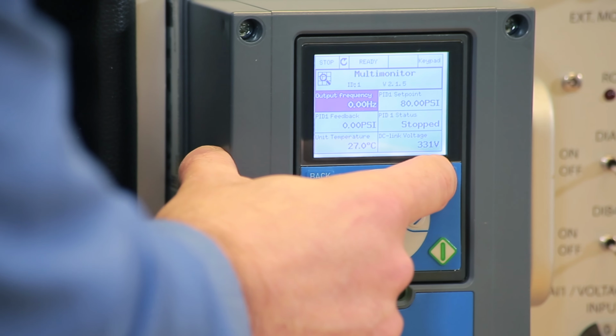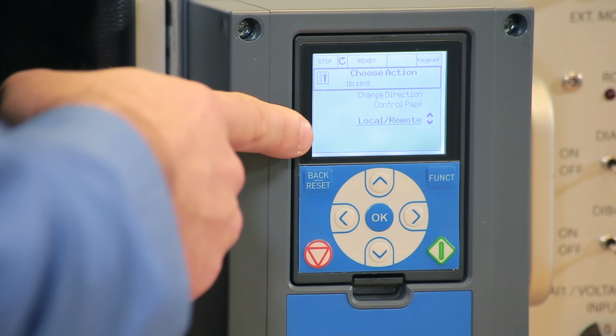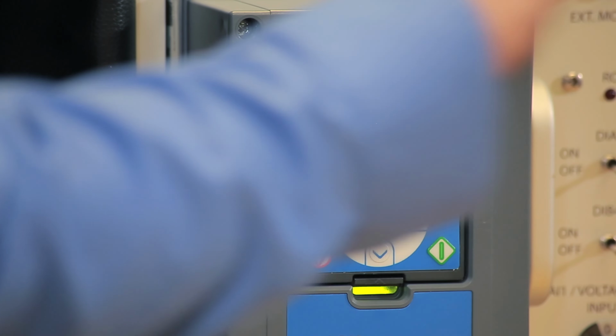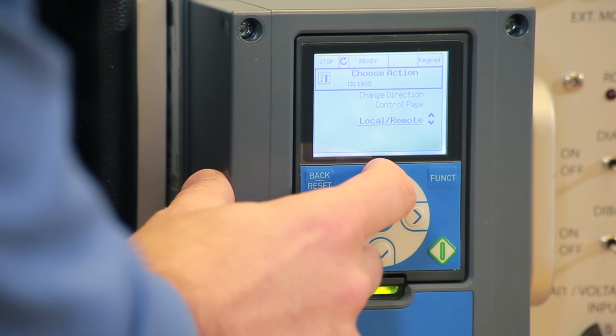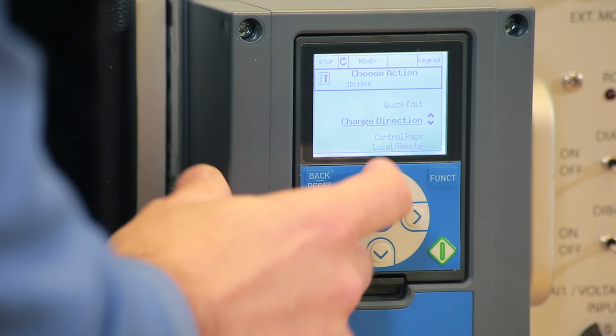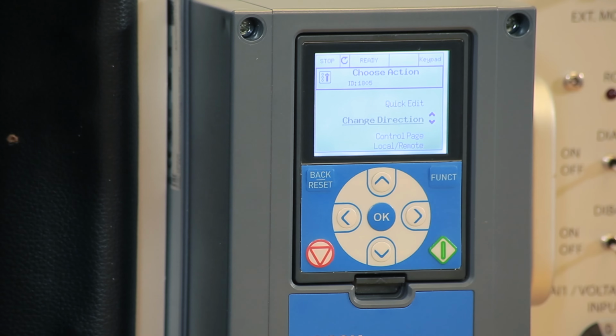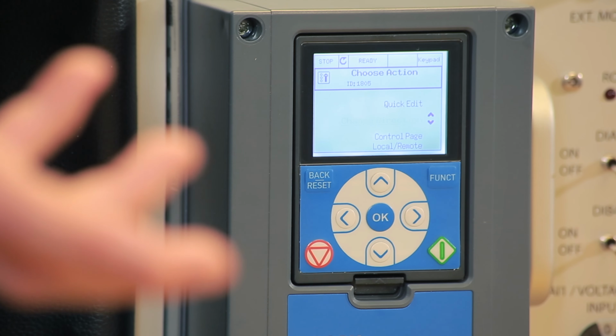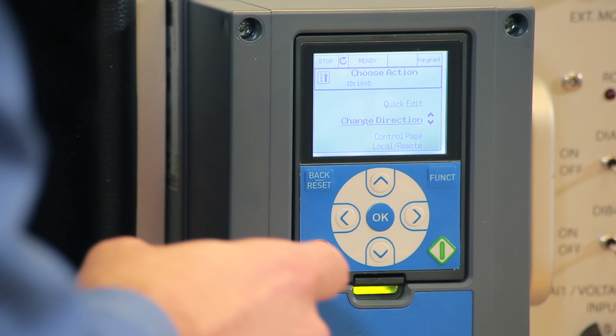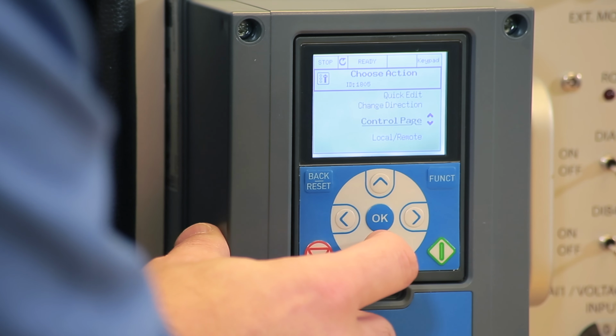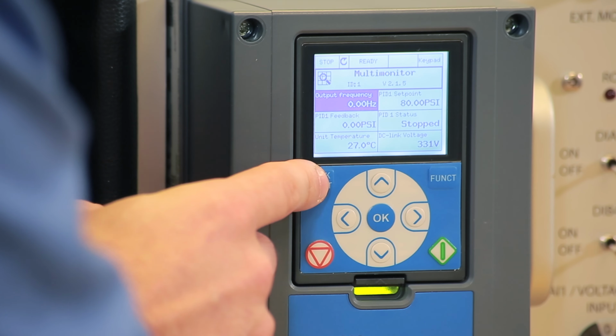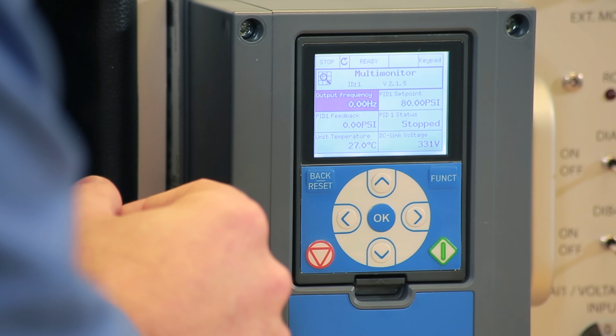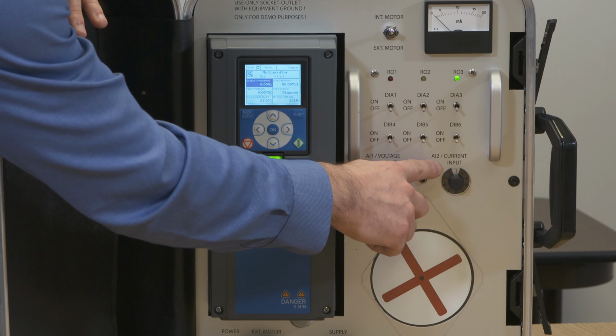The function button, if we press it, lets us change between local control and remote control, which are selector switches. Or we could change the direction of the motor so that it spins backwards. For example, if the motor is miswired and spinning backwards, you could go here and select change direction and the motor will spin in the correct direction. Very, very simple to do. So we're going to leave it at that and go back. So we have keypad control and PID feedback is with our analog input 2.